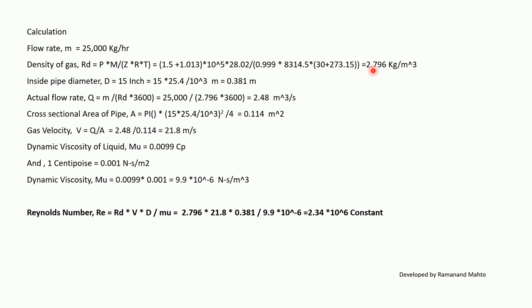Inside pipe diameter D = 15 inches, converting to 0.381 meters. Actual flow rate Q = M / (ρ × 3600) = 2.48 m³/s. Cross-sectional area A = π × D² / 4, with D = 15 × 25.4 mm, giving A = 0.114 m². Gas velocity V = Q / A = 21.8 m/s.